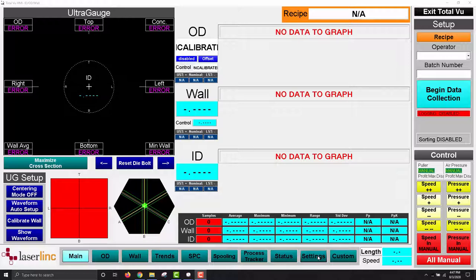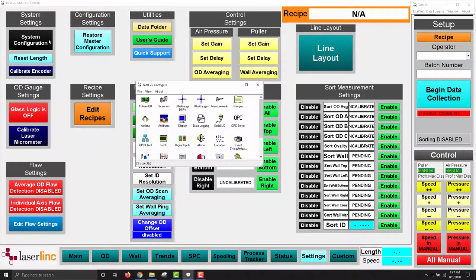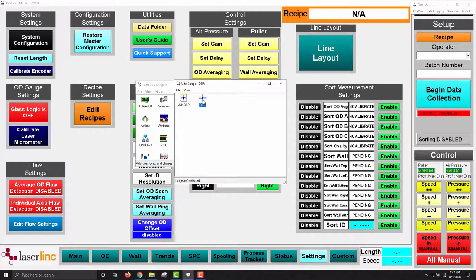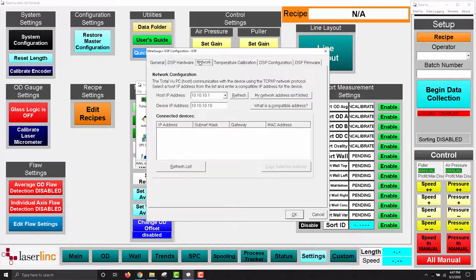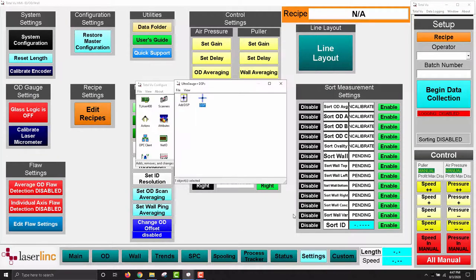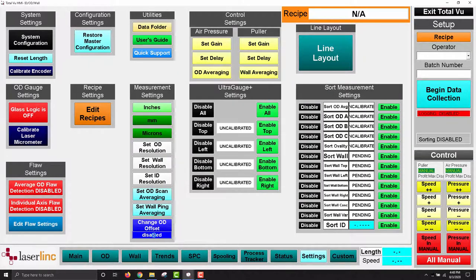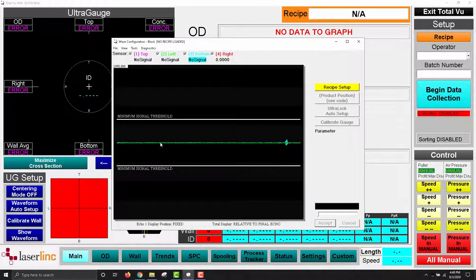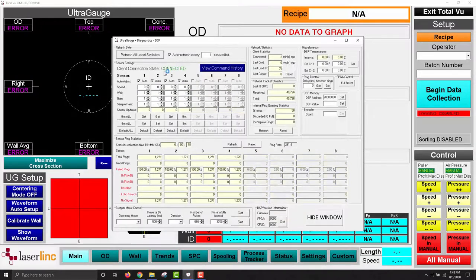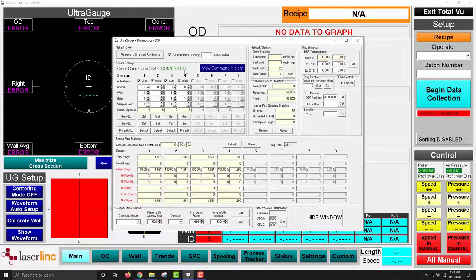Lastly, we'll verify that the ultra gauge and DSP are connected and communicating. Open full configuration and click on the DSP icon. And then click on the predefined DSP device. On the network tab, verify that the host IP address is correct and that the device IP address is set to 10.10.10.10. If everything looks correct, exit out of the full configuration menu and press control W to open the waveform window. From the top of the waveform window, select Diagnostics. And from the Diagnostics window, you should see a connected, green status, or a red, disconnected status, indicating whether or not the DSP is connected to Total View.